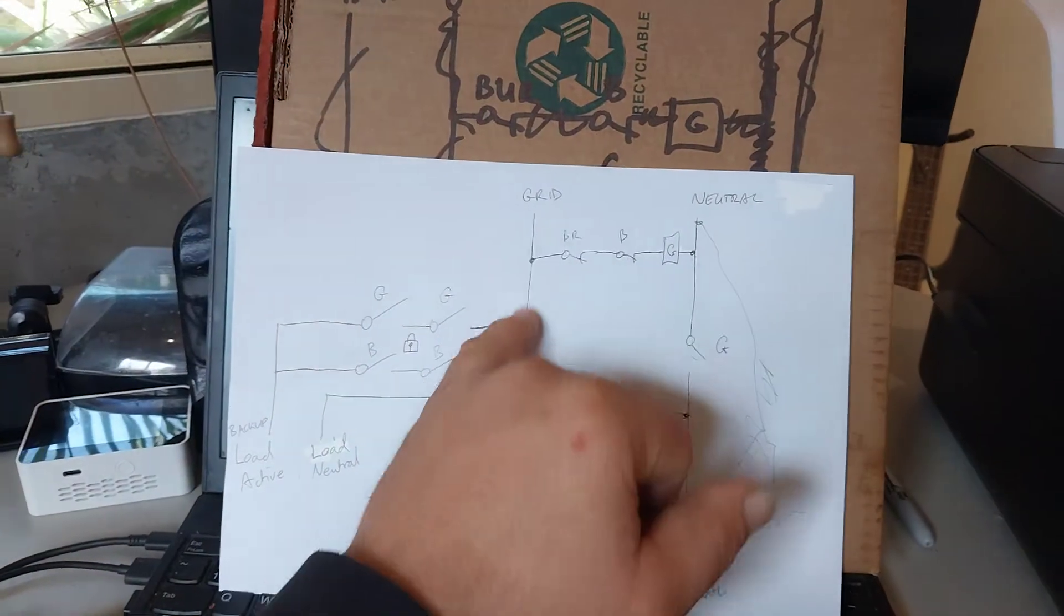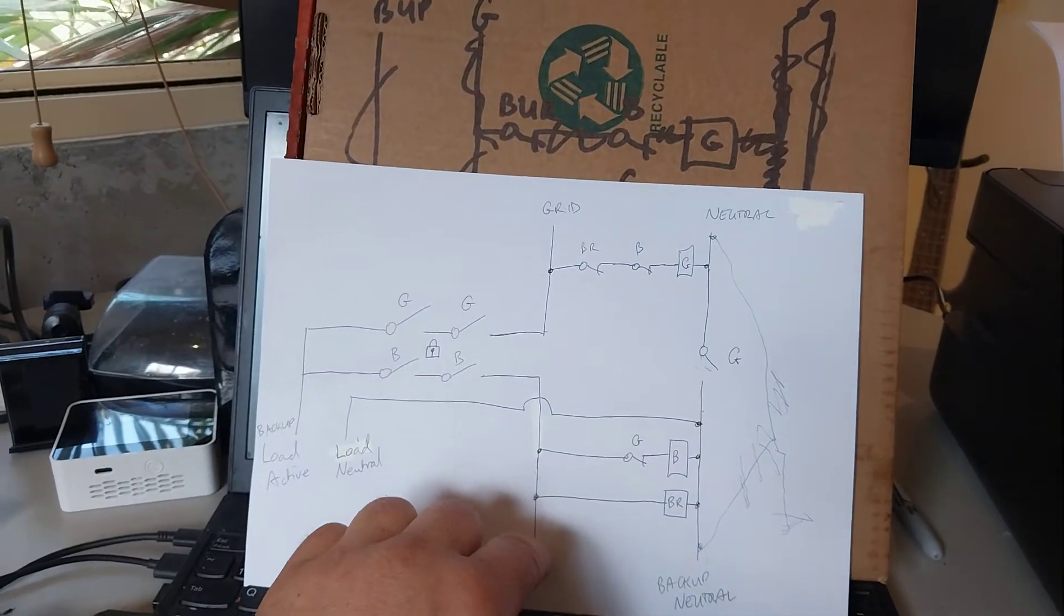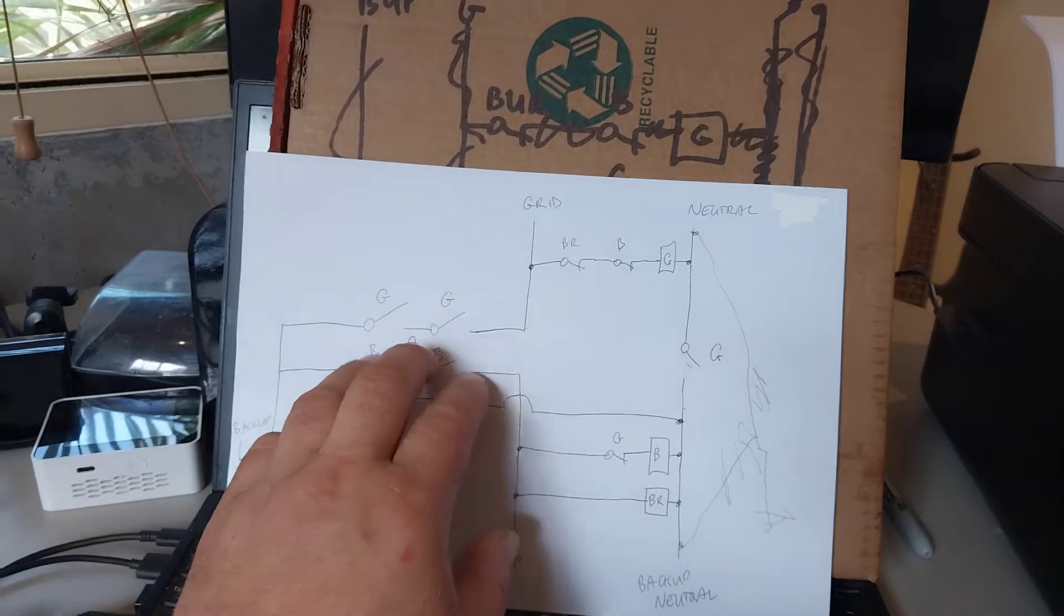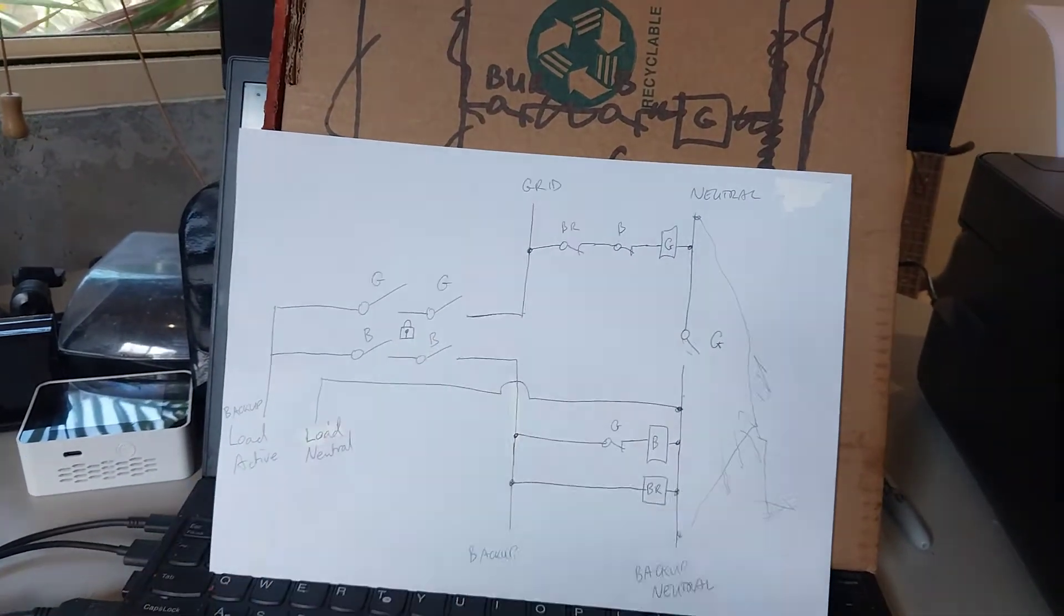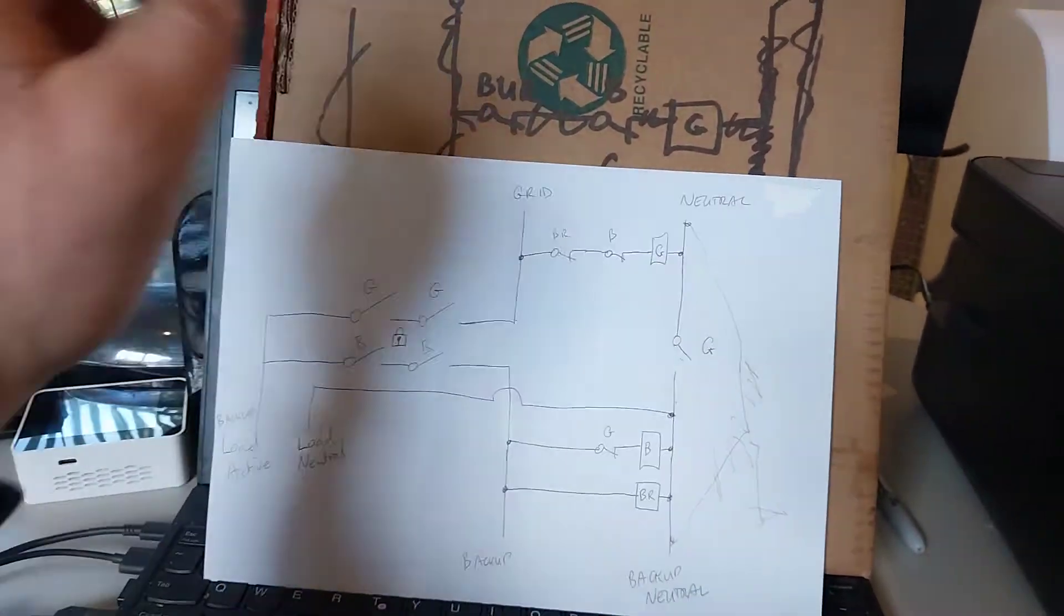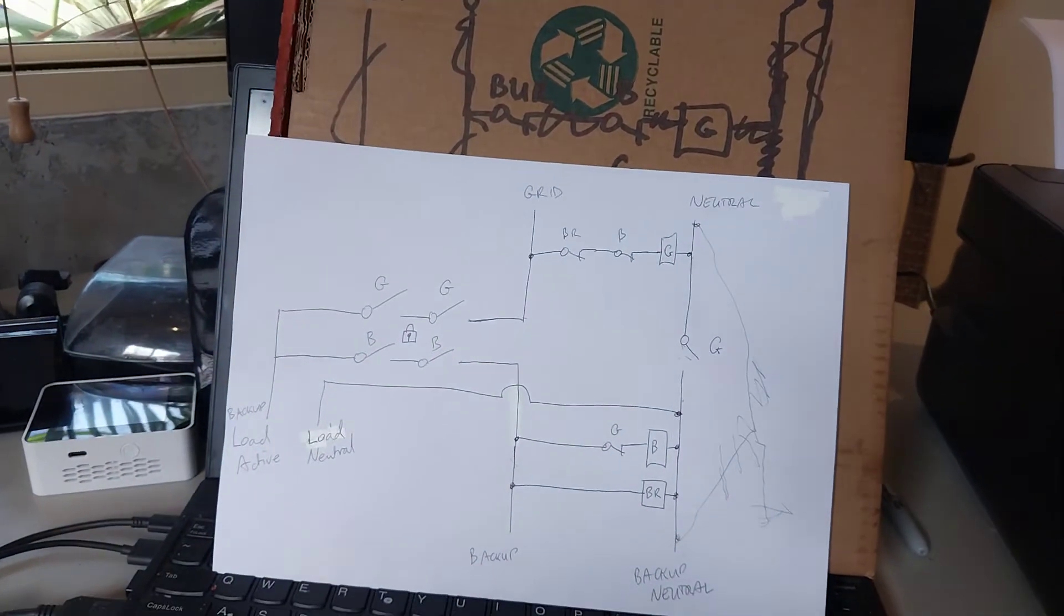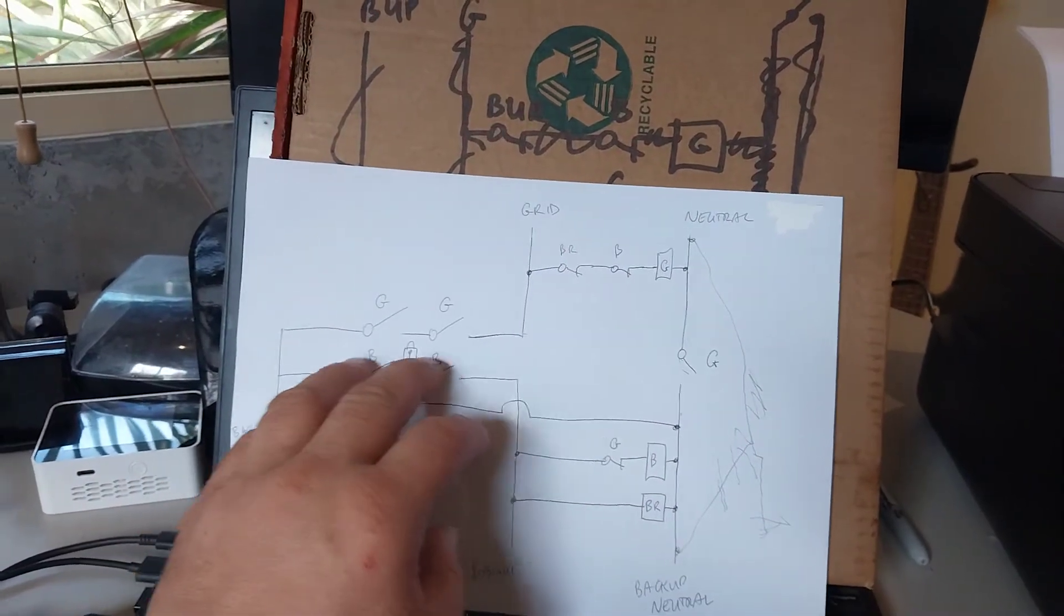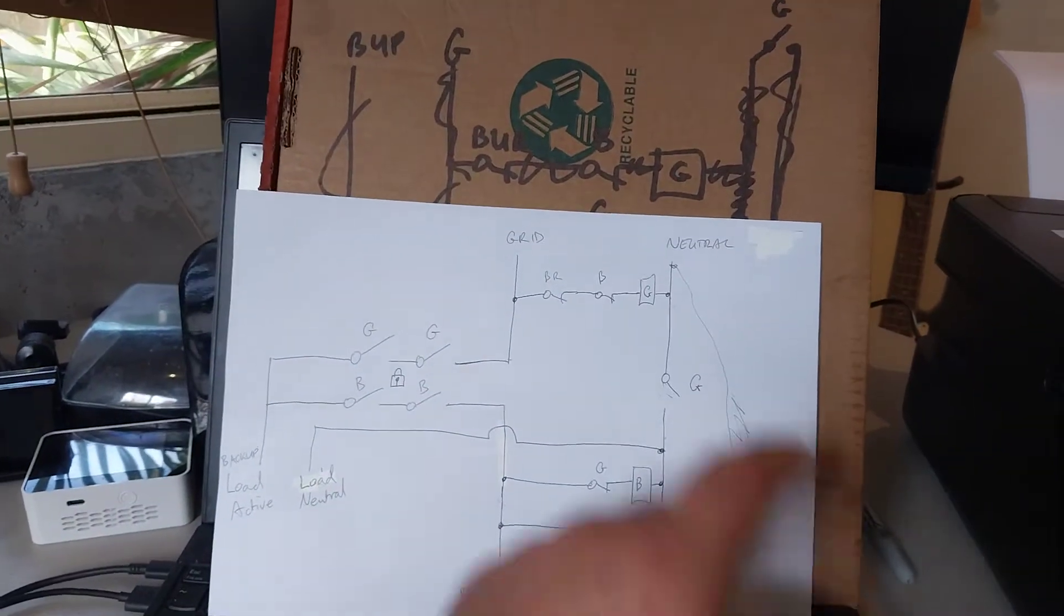So when grid is on we want these closed to supply, and vice versa for backup load. Close them but not at the same time. See there's a mechanical interlock. If they're closed together at the same time kaboom, you'll blow up your equipment because you've just joined your two power supplies together. So we don't want them to come on at the same time, we have a mechanical interlock.